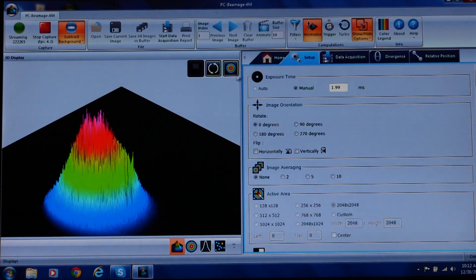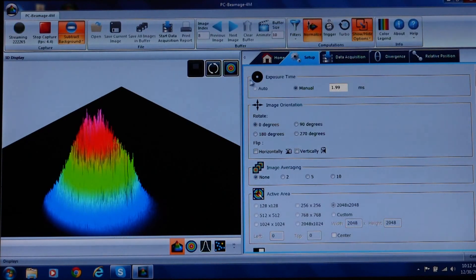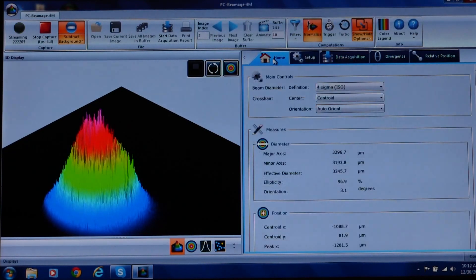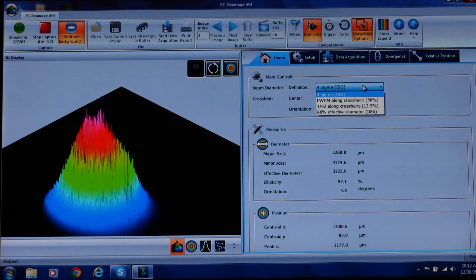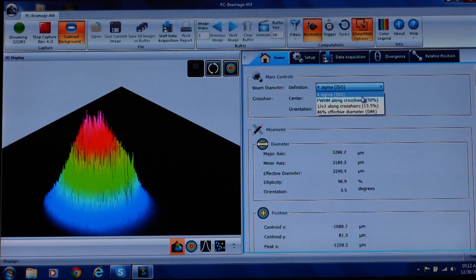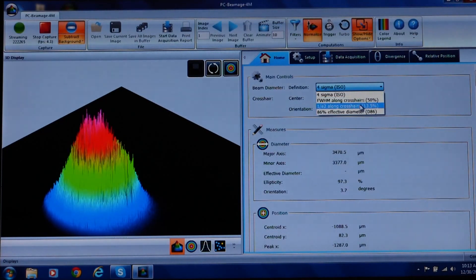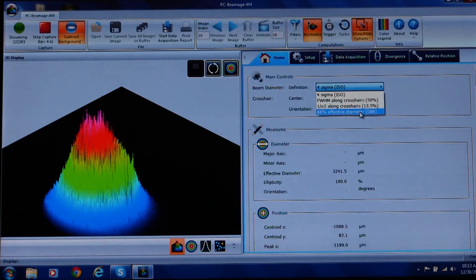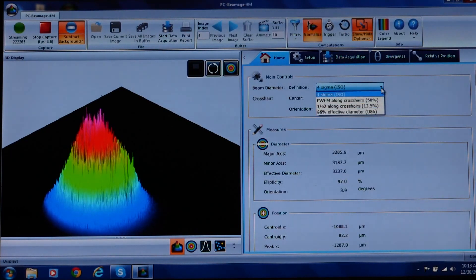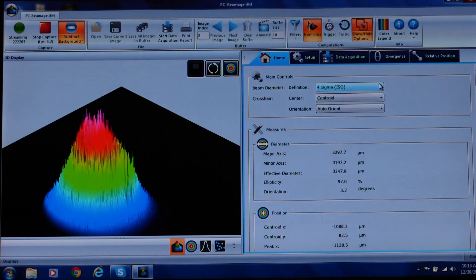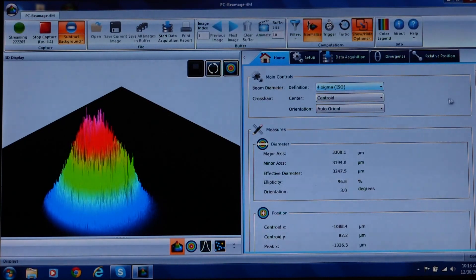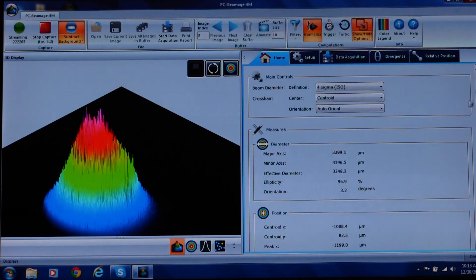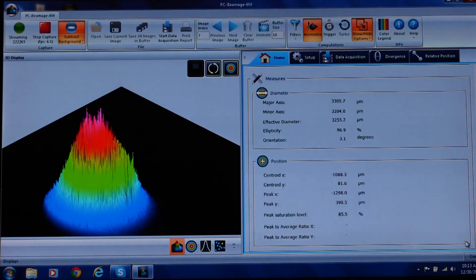Now let's return to the home tab where you can select the definition of beam diameter. You have four options. Four sigma, full width half max, one over E squared, or 86 percent effective diameter. We'll stick with the four sigma. I'll scroll down where you can see the measured values for beam diameter and position in micrometers.